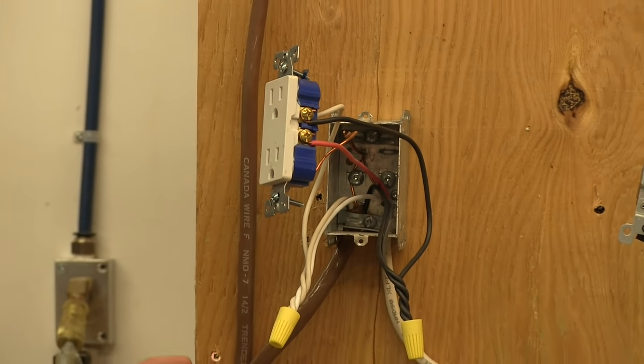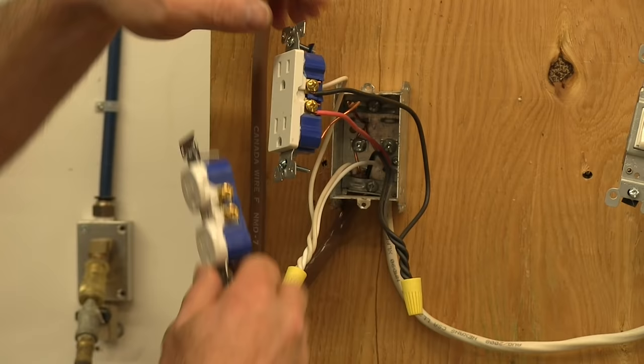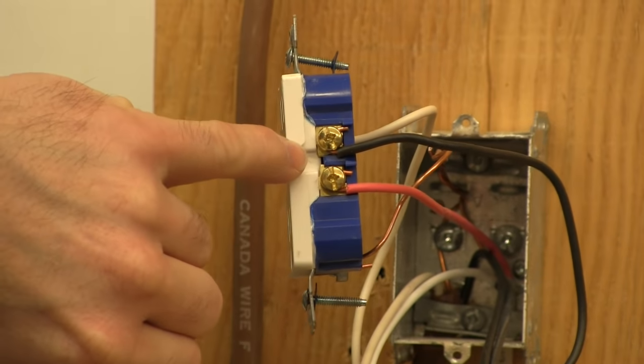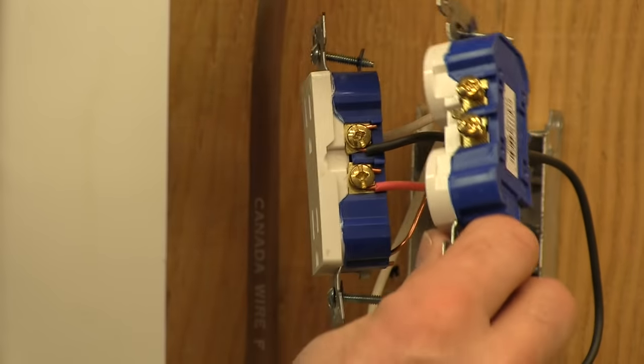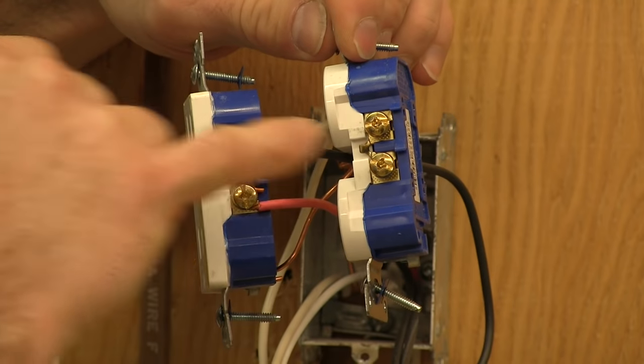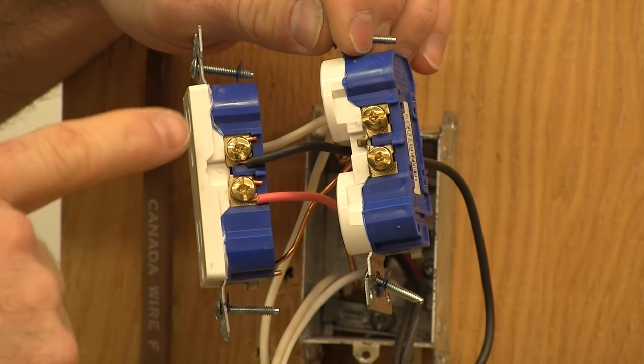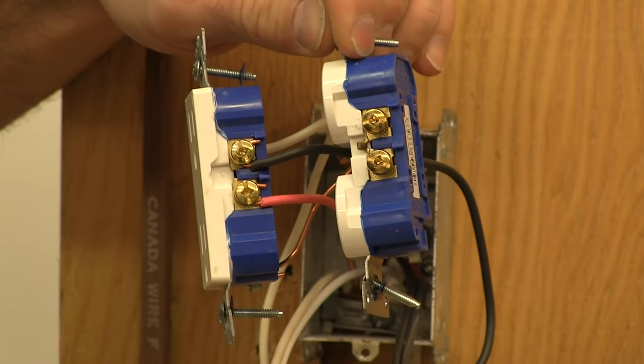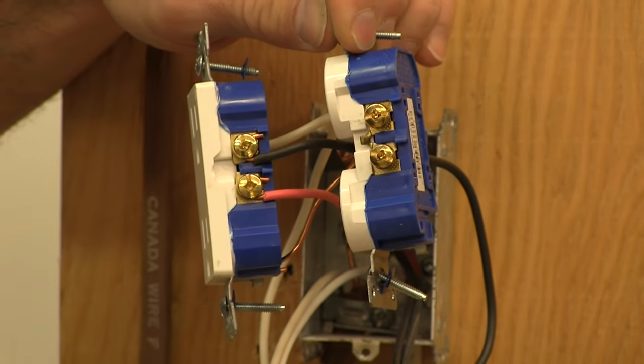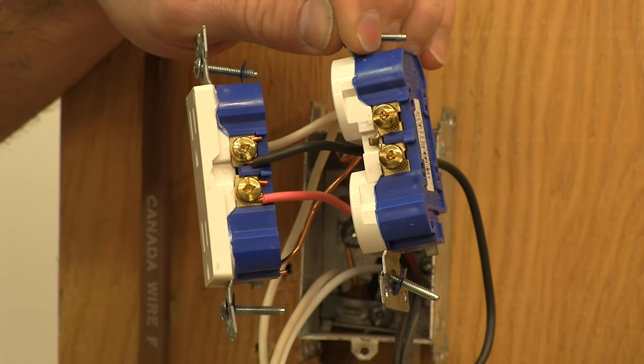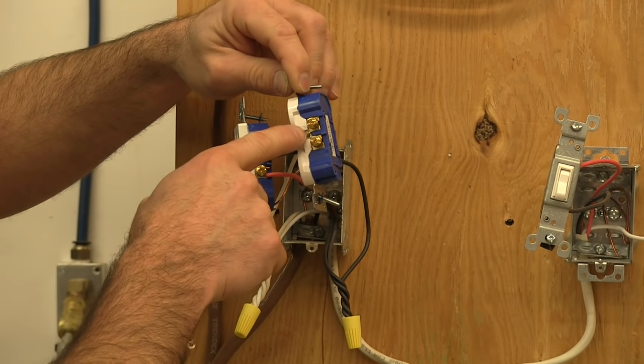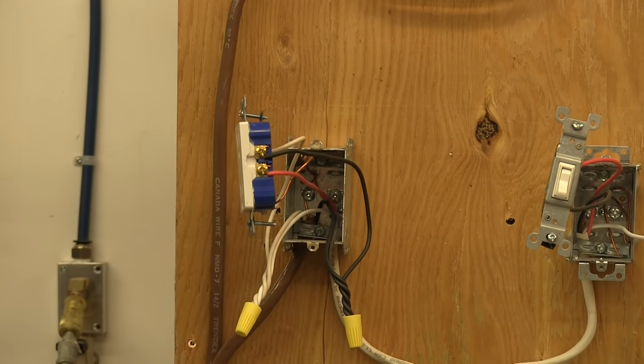Now the other thing you have to do if you're going to split a receptacle like this is, if you look right in here, there'll be a flat piece of metal in this space between these two screws. You can see it on this new one—you can see the tab right here. You need to break that tab out if you're going to have two different power sources operating two different receptacles. So that's very important. Otherwise you're going to have a big spark and boom and probably blow the breaker when you hit that switch. So make sure you take that tab out any time you're splitting the sources there.